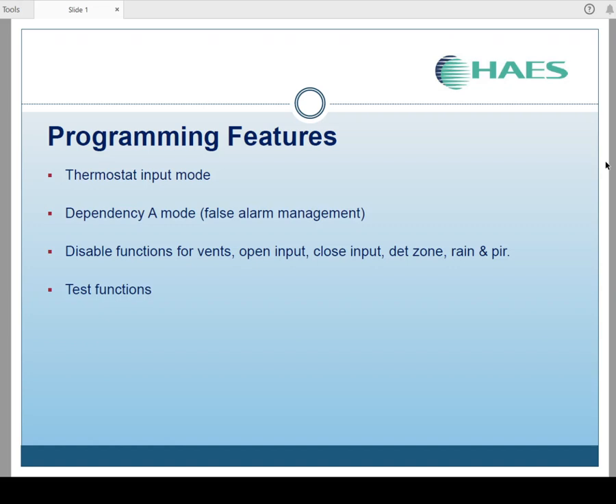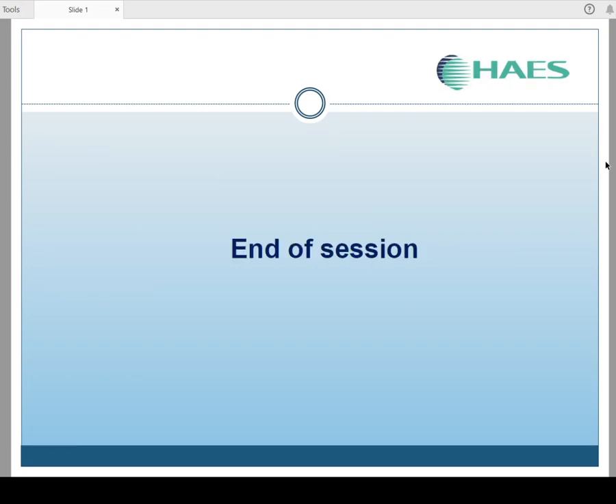Disable functions for vents, the opening inputs, close inputs, detector circuits, rain and PIR functions. They can all be disabled individually. And then you have your test mode function for your servicing. All these programming features can be accessed by turning on the programming switch inside on the DIL switch number 6, and then using the code supplied in the manual, you can set or change any of these functions. That's the end of this session.